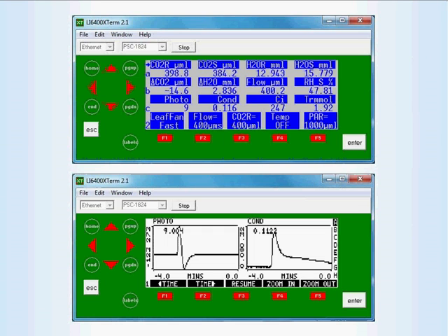Notice the decrease in the reference and sample chamber water vapor mole fractions from about 20 millimoles per mole shown previously down to about the 14 millimoles per mole shown here. Actually, the range is around 13 to nearly 16. The sample chamber relative humidity has also decreased from nearly 66% shown previously down to 48% shown here. The air temperature was about 25 degrees Celsius in both cases. The sample chamber airflow rate, the light, and temperature were left unchanged.